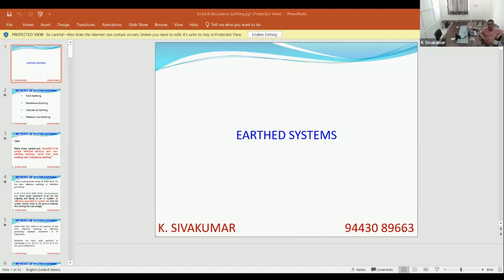Yes. So that is why separate earthing is required for instrument and electrical, while all earthing has the same potential? The very concept is, I would say, wrong. Mr. Gaurav Mishra's question: please study IEEE 1100. There is a publication called IEEE 1100, recommended practice for grounding sensitive electronic equipment. It does not recommend isolated grounding for sensitive electronic equipment or instrumentation equipment. This is a myth we are having. It should not be isolated. It should be interconnected with the grid, ultimately to the plant grid.